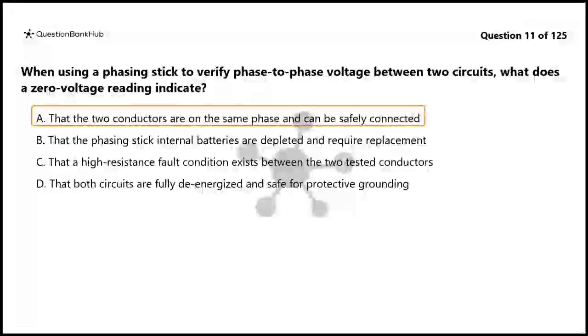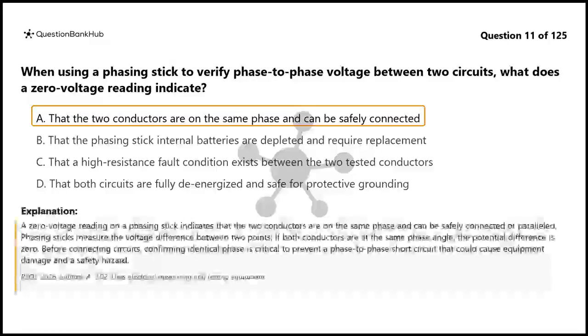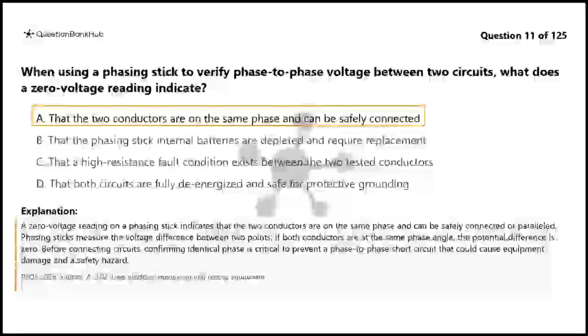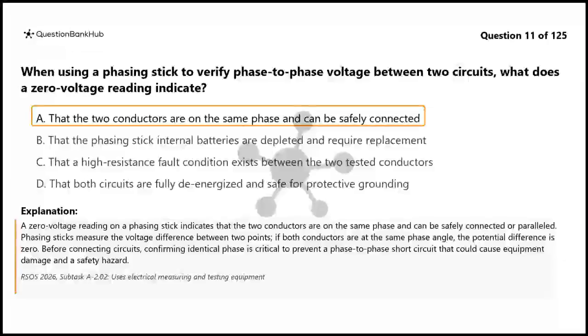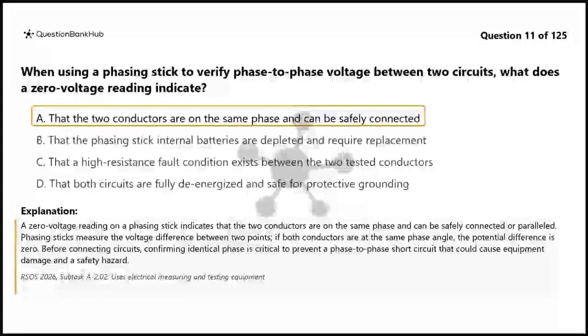The correct answer is A. A zero voltage reading on a phasing stick indicates that the two conductors are on the same phase and can be safely connected or paralleled. Phasing sticks measure the voltage difference between two points. If both conductors are at the same phase angle, the potential difference is zero. Before connecting circuits, confirming identical phase is critical to prevent a phase-to-phase short circuit that could cause equipment damage and a safety hazard.